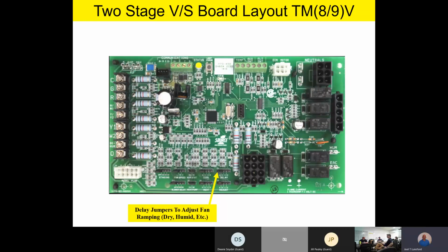But as a quick overview, when the fan starts out, for instance, in a cooling mode of operation, we'll just talk about the humid profile because, like I said, that's the one I happen to remember. Anytime you get a cooling call on the control board, it doesn't matter if it's first stage cooling or second stage cooling, the fan will start out at 50% airflow and hold that for about 1.5 minutes. It'll then ramp up to 82% airflow and hold that for another 6.5 minutes. Then if the call for cooling is still there, it'll ramp the fan up to 100% airflow until the call for cooling goes away. Once the call for cooling goes away, it ramps the fan down to 50% airflow, holds it for another 1.5 minutes, and then shuts the fan off.